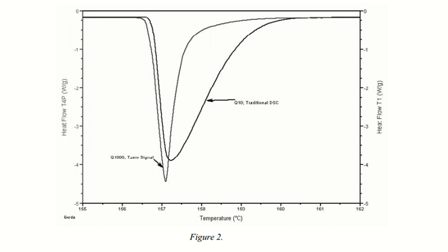The improved resolution of Tzero differential scanning calorimetry technology can be seen in this figure 2, a comparison of an indium melt with traditional and Tzero DSC technologies.